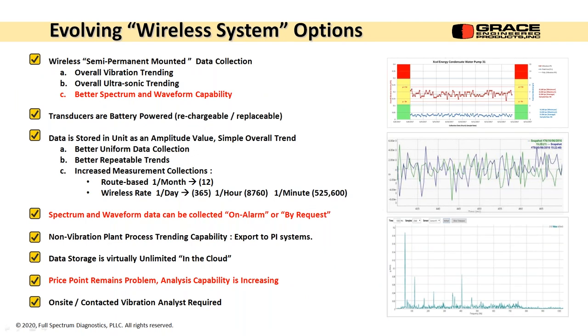Evolving systems, wireless semi-permanent mounting data collection. There are a lot of them out there that will do wired and battery powered, or you have the option of either. Data stored: spectrum and waveform can be collected on alarm or by request. That's really important because you don't want to be pumping spectrum every day. You'll wear the batteries out in no time. Price point is still high, and capability is increasing. So it's out there. It's elusive. Every time we want to do something, it's, hey, what if we do this? And that might cost a little more money. So it's pushing in the right direction, but it's got to be evolving all the time, which I believe it is.